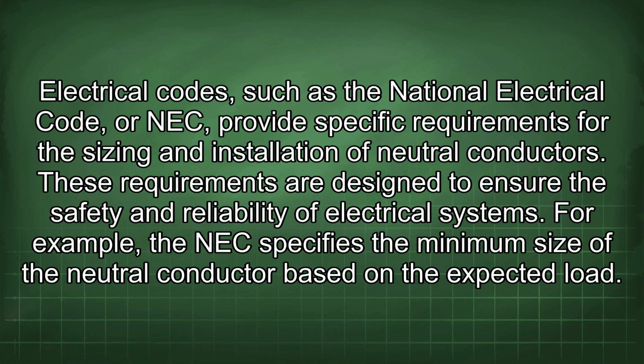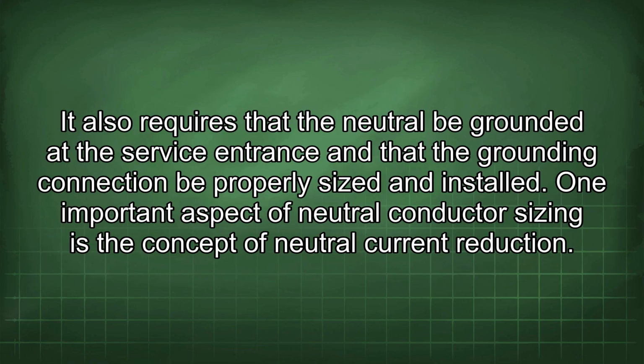Electrical codes, such as the National Electrical Code, or NEC, provide specific requirements for the sizing and installation of neutral conductors. These requirements are designed to ensure the safety and reliability of electrical systems. For example, the NEC specifies the minimum size of the neutral conductor based on the expected load. It also requires that the neutral be grounded at the service entrance and that the grounding connection be properly sized and installed.